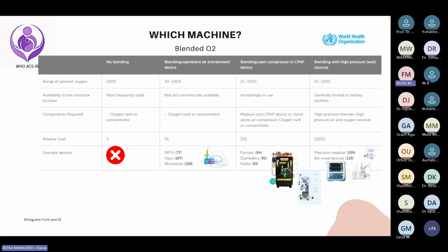The Diamedica, that's the one that we used in phase 1 and that we chose as first choice. Why did we do that? It's a little bit more expensive, but it's a medium cost CPAP. It has a standalone air compressor and a concentrator. So basically, it doesn't need any gas supply source, but needs electricity. And it also has a humidifier that is integrated here. So the Vayu also has a humidifier, but it's not heated. This one has a humidifier that is heated.